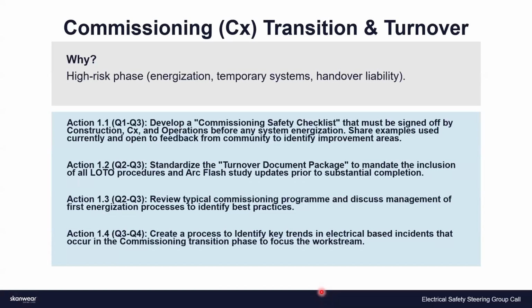And then there's another set of lockout tagout procedures for abnormal conditions. The abnormal conditions is what requires your qualified electrical workers, who have an incredible responsibility, because you have to assume that every single energy isolating device is not properly operating and that there is something else bleeding into the system. So the number of checks that you put into that goes dramatically up, and the equipment required to do it, the PPE and everything else, goes dramatically up.